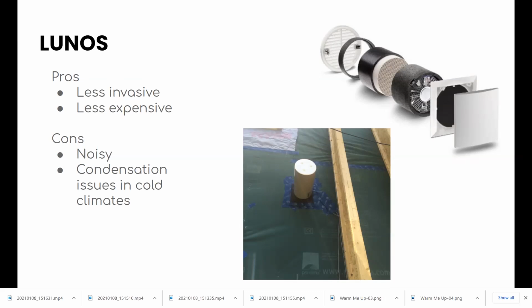And basically, in order to do the heat exchange, one will turn on intaking air for 70 seconds while the other one is letting the air out. Exhausting, thank you. And then after 70 seconds, they'll switch directions. So this one's been preheated as it exhausts.